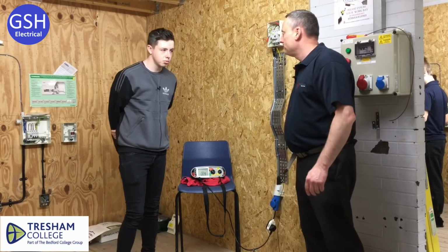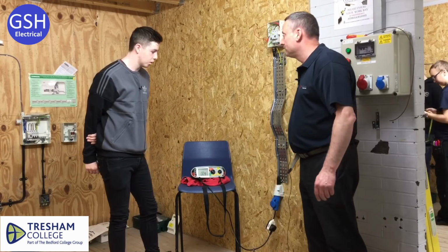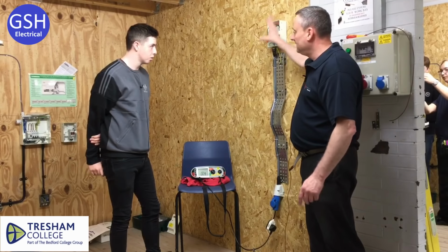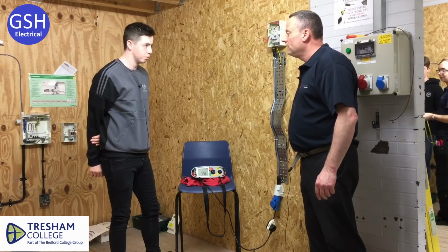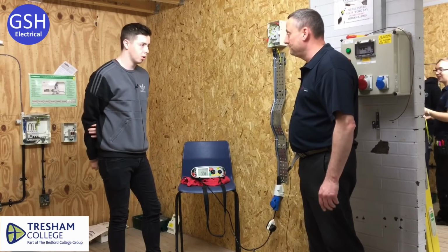What's the first test we're going to carry out, John? Polarity. Part polarity, during which test that we are carrying out first? Continuity of CPC. We are. Which conductors do you link together in the consumer unit? Line and CPC. Line and CPC. And are you going to record that result? No, we're not. It's part of that polarity test.